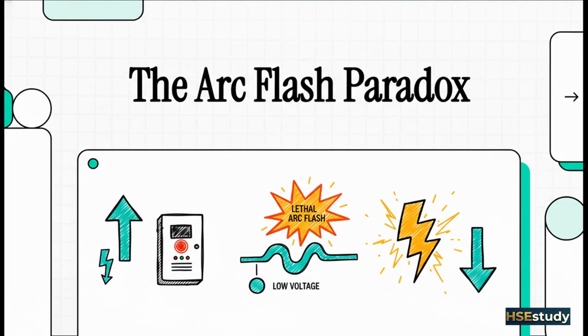As electricians, we're all taught the same thing. Higher voltage equals higher danger. It just makes intuitive sense, right? But what if I told you that when it comes to arc flash, that intuition is dead wrong? The actual physics of incident energy tell a completely different story. And frankly, it's a much more lethal one. So let's break down the engineering behind this crazy paradox.